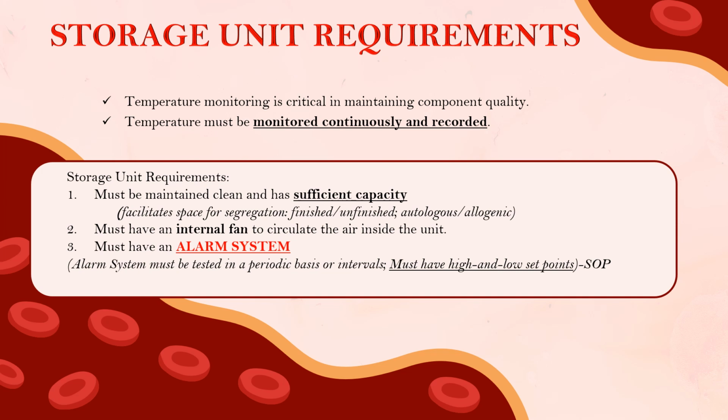One of the most important and critical factors is temperature monitoring, because failure to adhere to proper component storage temperature may threaten the viability and clinical effectiveness of these units. That's exactly why, class, storage temperature must be monitored continuously and must be diligently recorded.